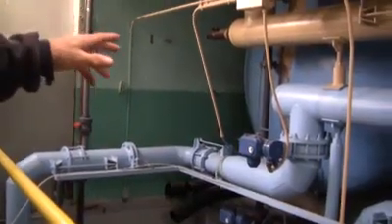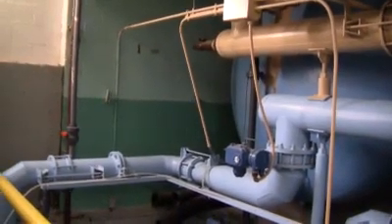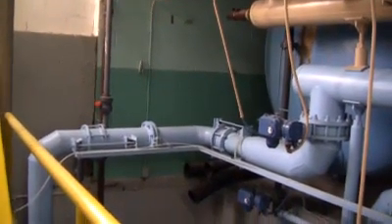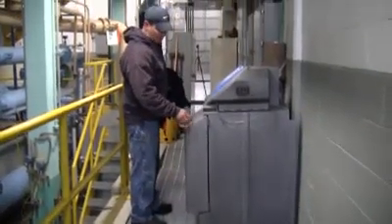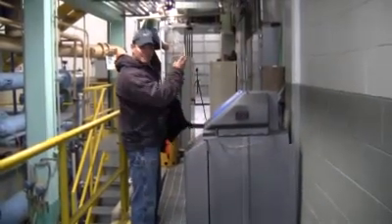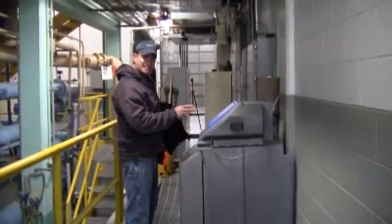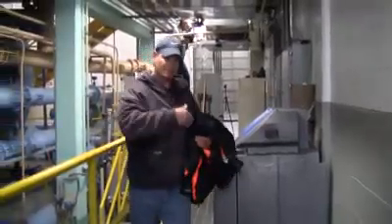And then it goes into these rapid sand filters. This is where the little tiny particles are removed if anything gets past the secondary treatment process. This is where we sample the effluent. We sampled before it came in, and now we're sampling it going out to see how much we've removed. We usually get about 98.9% removal from this treatment plant.